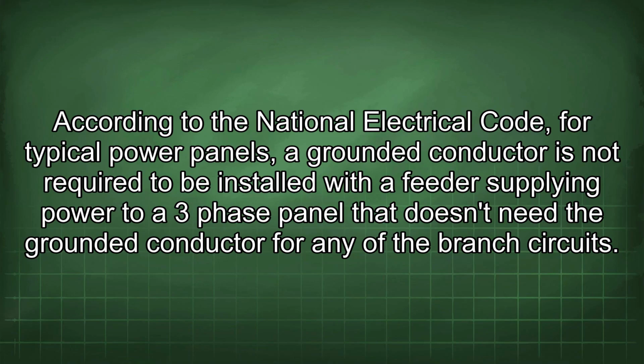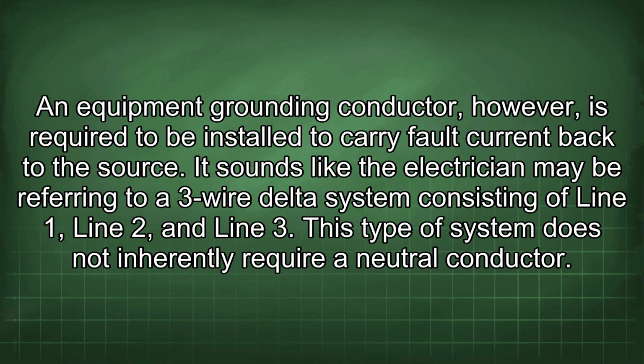According to the National Electrical Code, for typical power panels, a grounded conductor is not required to be installed with a feeder supplying power to a three-phase panel that doesn't need the grounded conductor for any of the branch circuits. An equipment grounding conductor, however, is required to be installed to carry fault current back to the source.